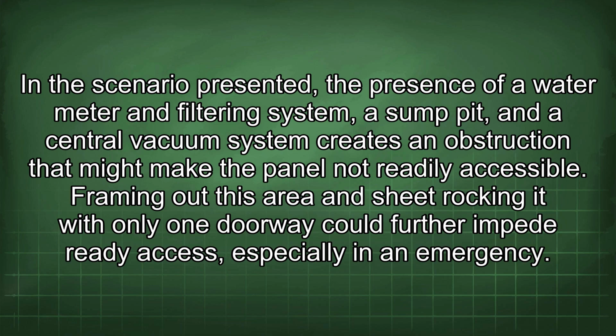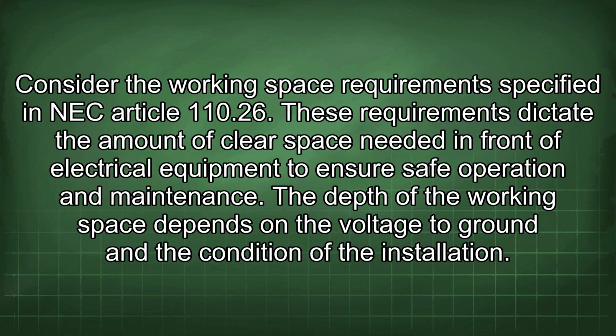In the scenario presented, the presence of a water meter and filtering system, a sump pit, and a central vacuum system creates an obstruction that might make the panel not readily accessible. Framing out this area and sheetrocking it with only one doorway could further impede ready access, especially in an emergency. Consider the working space requirements specified in NEC Article 110.26. These requirements dictate the amount of clear space needed in front of electrical equipment to ensure safe operation and maintenance. The depth of the working space depends on the voltage to ground and the condition of the installation.